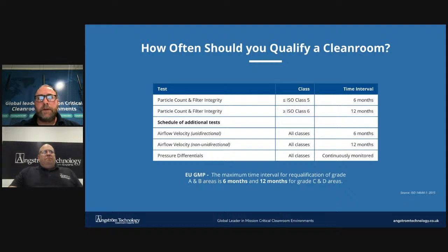Okay, so good manufacturing practice, EU GMP, describes a minimum standard a medicines manufacturer must meet in their production processes. EU GMP Annex 1 details maximum permitted particle concentrations for classification for at-rest and in-operation states for sterile manufacturers. The maximum time interval for requalification of grade A and B areas is 6 months and 12 months for grade C and D areas.